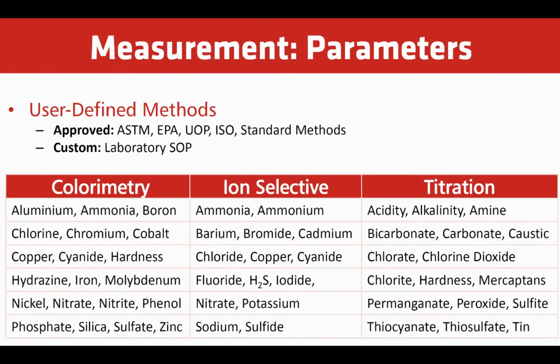With the AccuSeries analyzer, we tend to use previously user-defined methods. Some of these are ASTM, EPA, UOP, ISO, or standard methods. Or we can do custom applications, where a custom application is done at a certain customer site, and if they will share that lab method, we will set up our analyzer to do the same in the field. Colorimetry, we can do ammonia boron. We can also do this if it's higher levels with ion selective electrode. We offer various titrations for acidity, alkalinity, amine value. Again, going back to colorimetry, as you can see, it's really A to Z what we can offer. And we will, depending on the application, either offer it as a titration, colorimetric, or ion selective. That's all based on the actual application and possible interferences that may be there, etc.